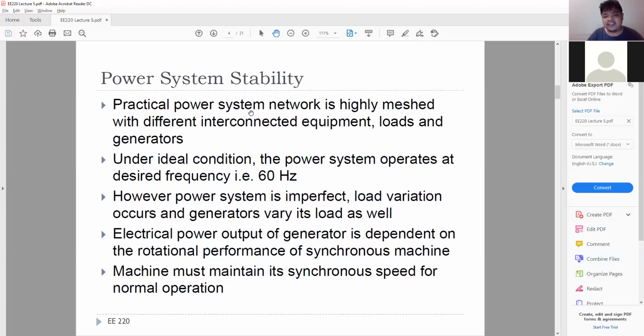Now currently, the range stated is that we should be operating within 59.7 to 60.3 Hz, or plus or minus 0.5%. However, that's more of a tolerable range.